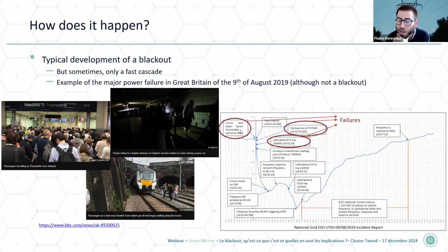You had a fault on a transmission line, a single fault, and that was cleared normally in 74 milliseconds, so a normal clearing time. So normally the system should have stayed stable, but some generating units were incorrectly disconnected by their protection systems. A wind farm and a CCGT were disconnected. And you can see on this picture the frequency transient. That led to a severe frequency transient, and so low frequency demand disconnection to stabilize the frequency. So in that case, load shedding was not due to a slow cascade followed by a fast cascade, but directly due to a fast cascade: several failures directly leading to an electrical transient.